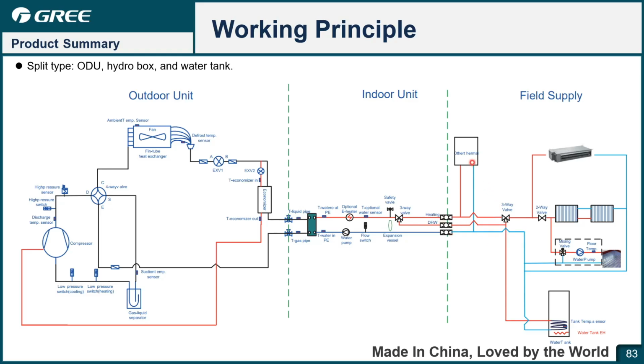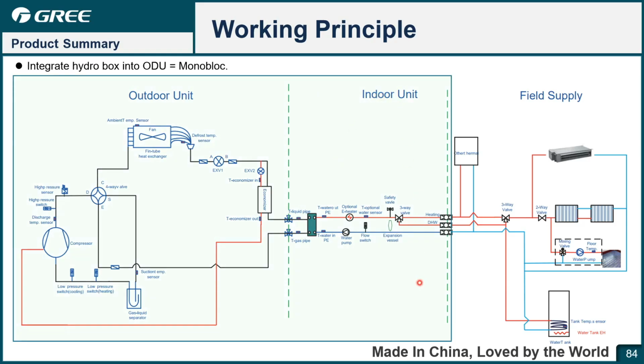And there is other thermal, such as the gas boiler. If they want to use a backup heat source, they can connect with the water system. So this is the split type working principle. However, if we put the outer units and the indoor units together, integrate the hydro box into outer units, then you can get the monoblock.